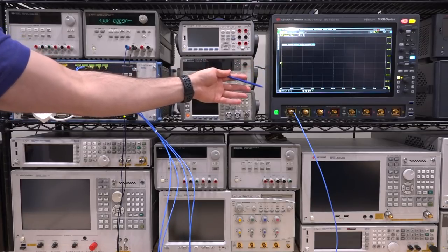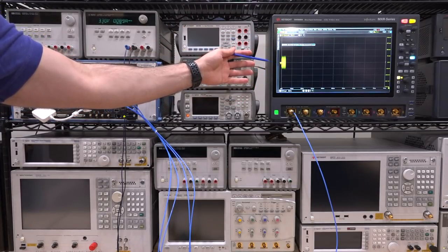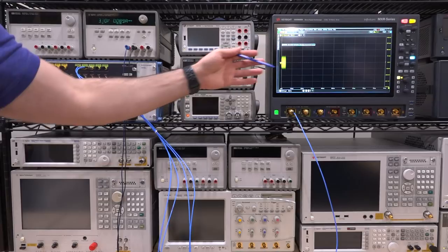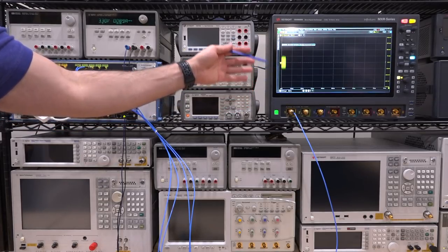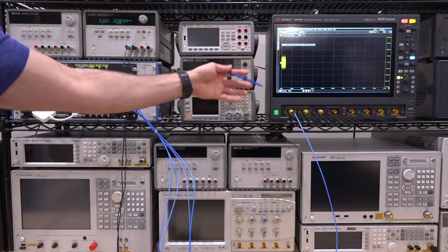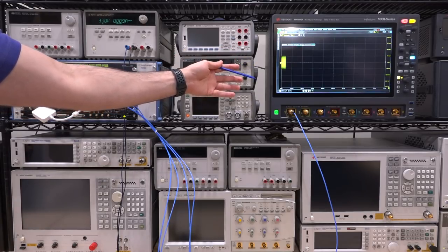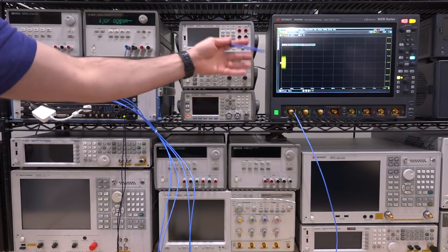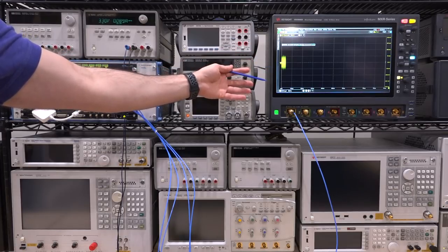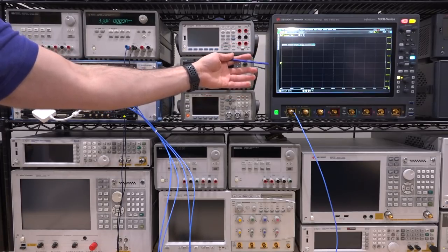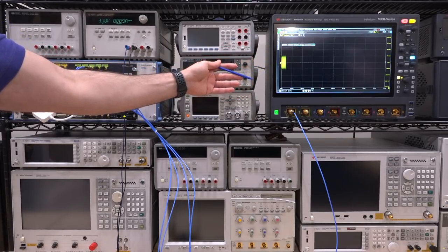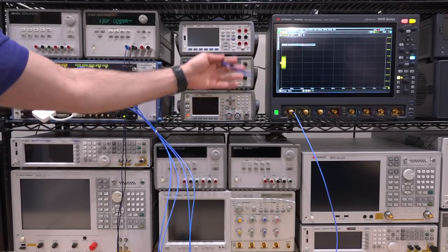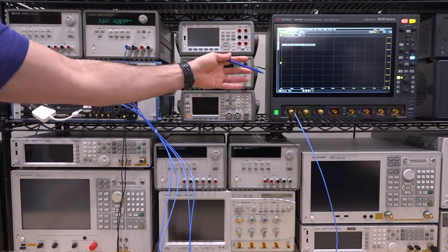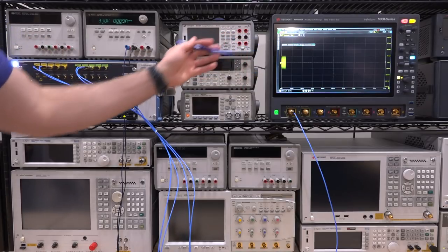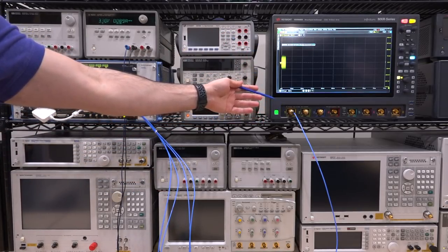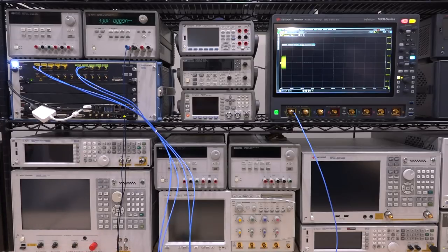On the right side, we have a Keysight MXR608A, which is a 16 gigasample per second, 6 gigahertz, 8-channel oscilloscope. I've done a full teardown and review of this instrument as well. Because it has a completely independent acquisition board for each individual channel, we basically can do a huge amount of computation with the VSA software that this is compatible with. This also has digital down conversion built into it, which lets you do 2 gigahertz of instantaneous analysis on the VSA too. So when you have 8 channels connected to the VSA, you can do MIMO, you can do a lot of computation in the back end. We'll take a look at that here. In this case, we're only really using one of the channels, but nonetheless, that's of course possible.